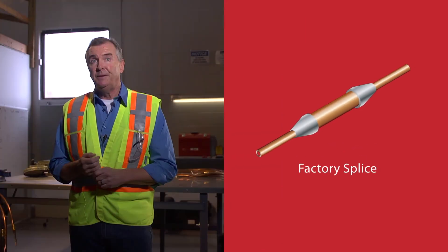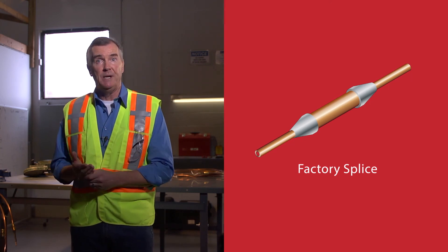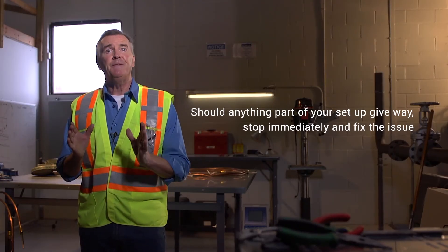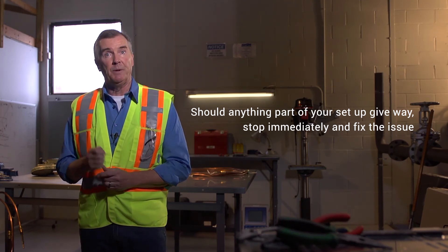Sometimes a factory splice may be present on the cable. These are the only situations when manual assistance should be used, as splices need to be carefully pulled over the wheels to avoid them from getting hung up. Remember that your pulling tension limits will change when there is a factory splice involved in the pull. In the event that a sheave wheel or support does break or come loose, immediately stop pulling and fix the equipment before proceeding. Ignoring a broken or loose support can compromise your whole installation.